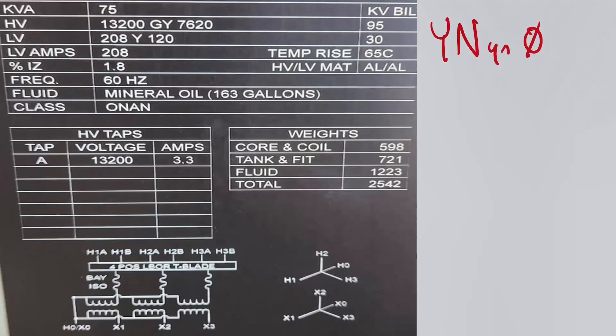And the reason why it's labeled like this is because the primary is always capital letters. And so this is our primary right here. And so it's a Y and the neutral is brought out, it is accessible. You can also see that if you look over here, your HO and XO are commonly bonded and they were brought out of the transformer. So that's why this is a Y,N, and both letters are capital, because it's the primary. Now the primary is also assigned by default at a 12 o'clock position. So it doesn't matter which phase you look at from the primary to the secondary, it just matters that you're looking at the same phase.